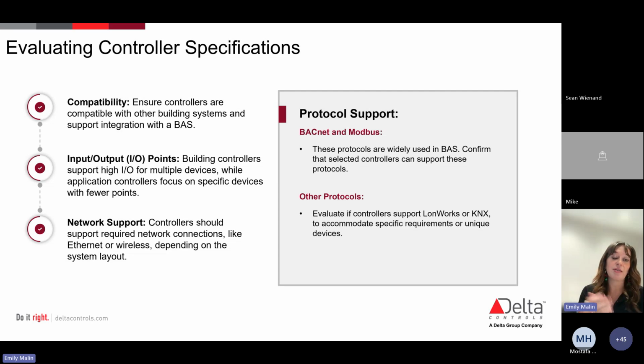And that final point there, actually, it's not the final point, the point that's in the middle, is about the inputs and outputs. And that was, again, what we talked about in BAS 102. We got you all the way to the point of being able to build that points list as an engineer. So once you have that, you know how many points are going to be included, especially the real IO points that you're going to need to physically wire up to that controller. Moose took us through virtual, which is not really super applicable here. If you have 6 inputs and 4 outputs, you know that you're going to want a controller that can actually handle that much input output, or, excuse me, add-on modules for that. It's just a way to start sizing your controller based on what you are actually controlling.